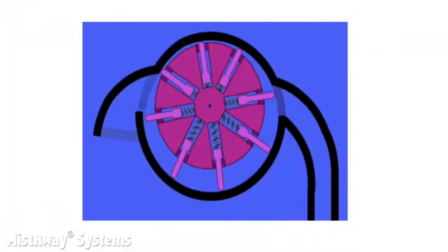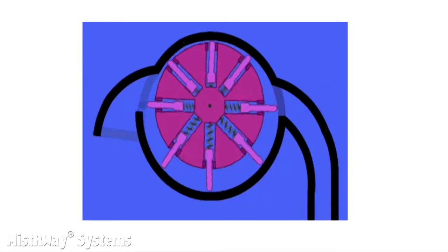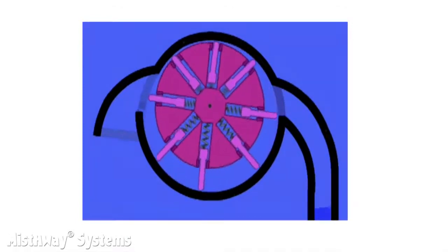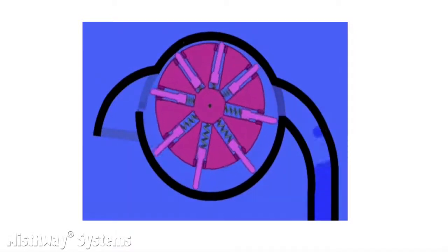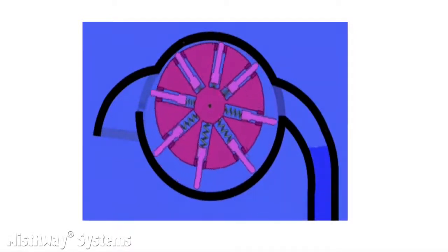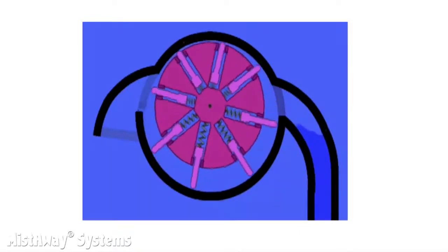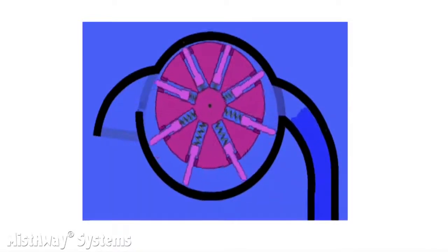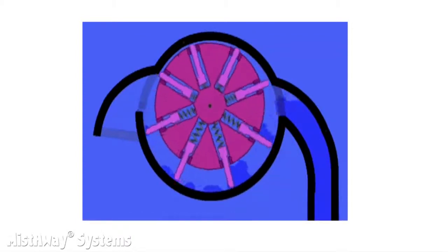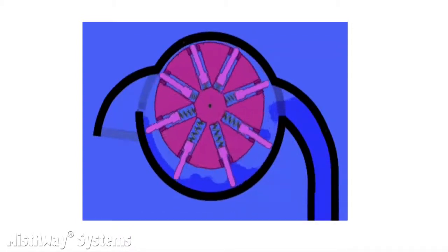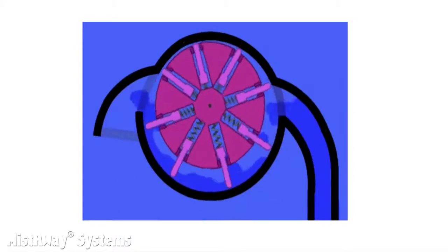Now let's talk about how a rotary vane pump works. Look at this animated cutaway of a rotary vane pump in action. The intake is on the right side, the discharge is on the left. Inside, there is a circular rotor rotating inside a larger circular cavity. The centers of these two circles are offset. The vanes slide into and out of the rotor, creating a seal on all edges and vane chambers that transfer the fluid from the inlet to the discharge.